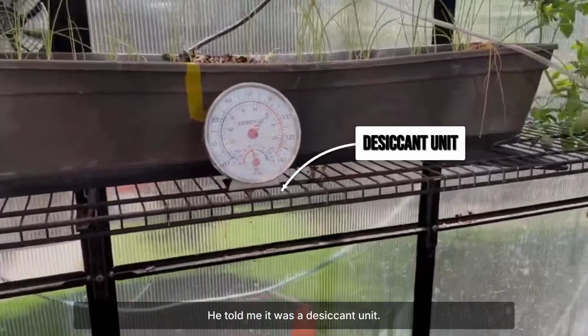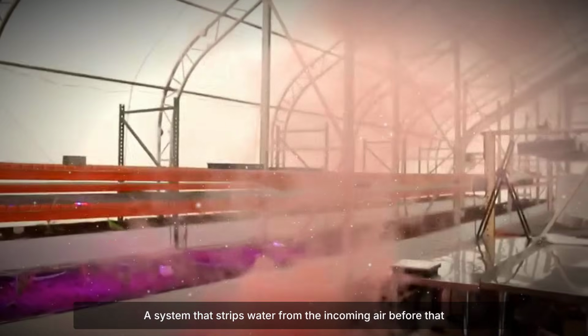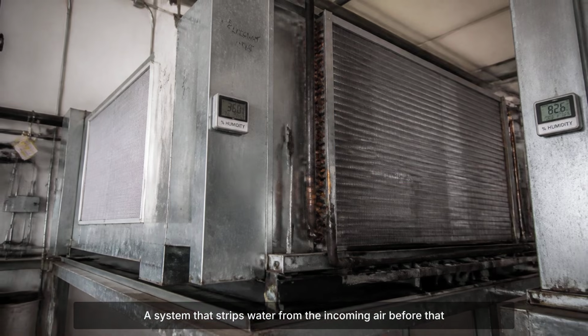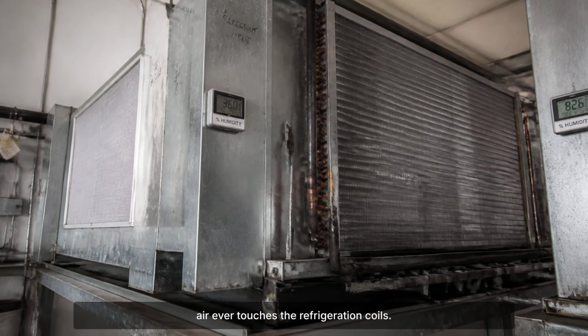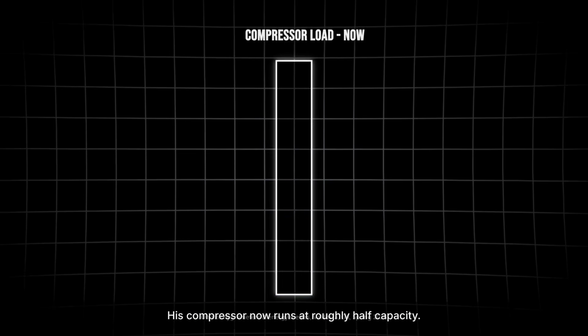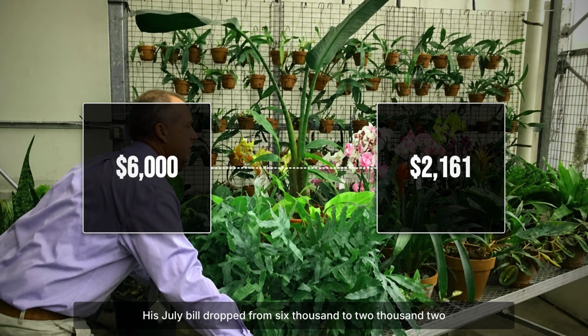He told me it was a desiccant unit, a system that strips water from the incoming air before that air ever touches the refrigeration coils. His compressor now runs at roughly half capacity. His July bill dropped from $6,000 to $2,200.